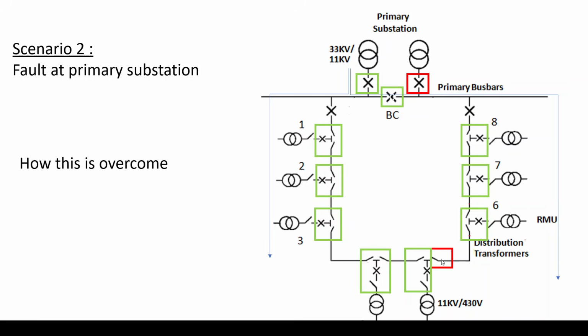network, my ring network is open. It's not continuous. So this one still it's open. So I would close this bus coupler and the power would flow from here all the way to feed the loads which were disconnected earlier due to the fault happening here. So the RMU since has helped me to connect all my loads in a ring manner, and now I'm using the advantages of having my loads connected in a ring manner. Therefore, I have overcome this scenario by closing the bus coupler and feeding all these loads. So as we saw, a fault, the first case that we had was a fault at the primary substation. We assumed that this part was faulty, and immediately we have overcome this by using the bus coupler here to feed the other part.